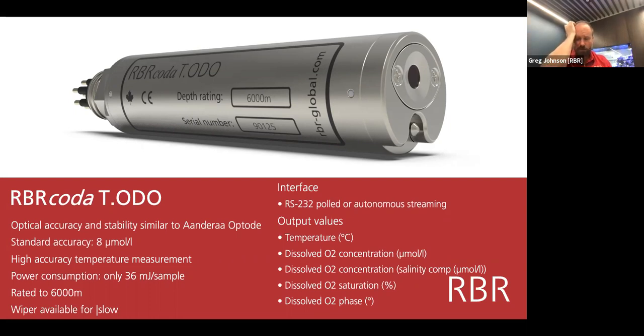And we have two different outputs of that. One is a measurement that is corrected for temperature. The second is corrected for temperature and also corrected for salinity, because the salinity of the water makes a difference to the oxygen concentration. The salinity value that you're deployed in can be set inside the instrument. So you tell the instrument the salinity here is 35, and the instrument will then take that into account.